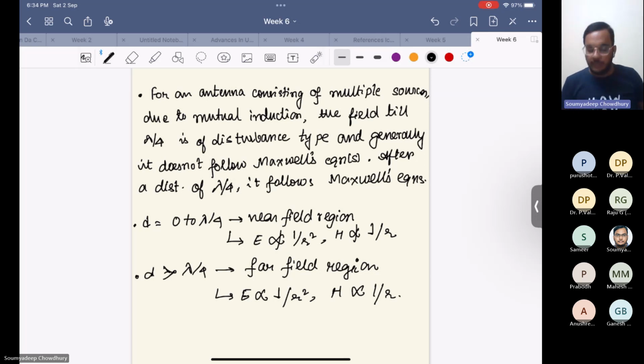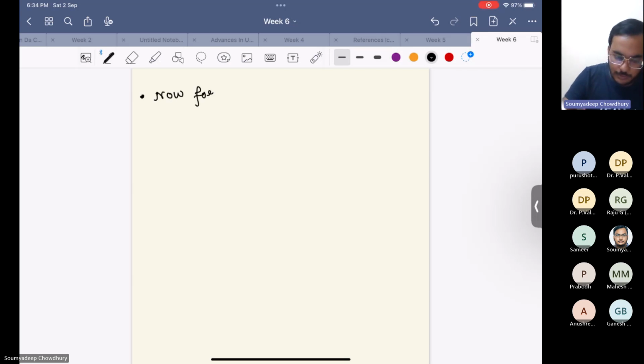So now I will talk about impulse voltage grounding. In impulse voltage grounding, basically this substation grounding has two parts: one is for impulse voltages and another is for power frequency voltages.